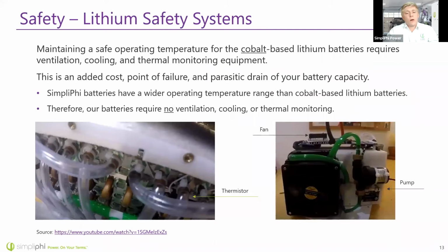Now let's talk about other batteries that are not lithium iron phosphate. Because they are thermally unstable, they need added equipment such as thermal monitoring equipment, thermistors, ventilation, a fan within your battery setup, and cooling equipment, often a liquid cooling system with a pump that circulates coolant.